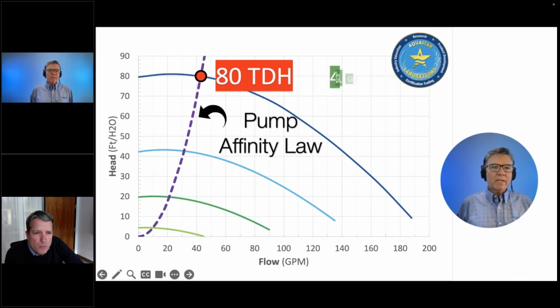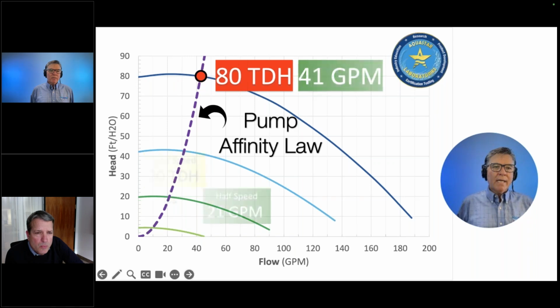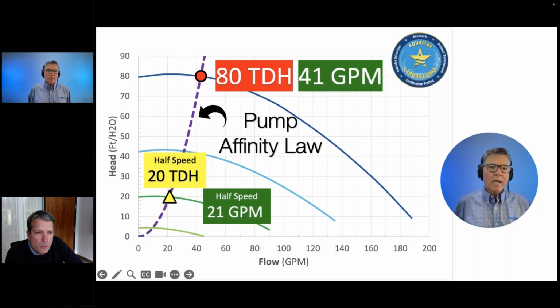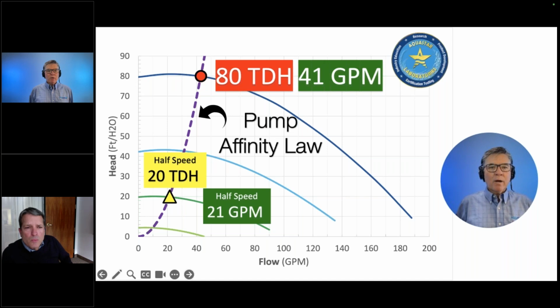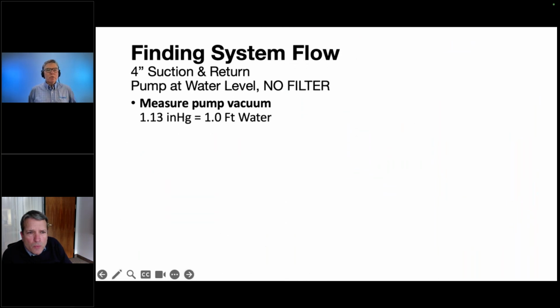Now we apply the affinity law. If we look at half speed, it's down here at 21 gallons a minute, and the TDH dropped from 80 to 20. So you see this relationship. This is the case where you put a big pump on small pipe, and it's into cavitation and basically on a mode to self-destruct. So that's a problem where we have to slow down that pump so it doesn't cavitate, which is a good solution, but it takes some know-how.